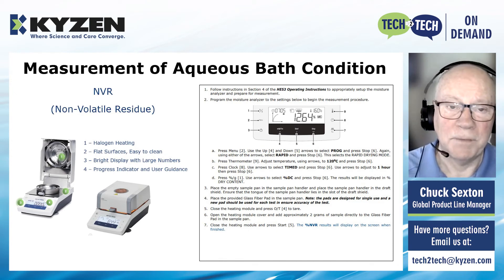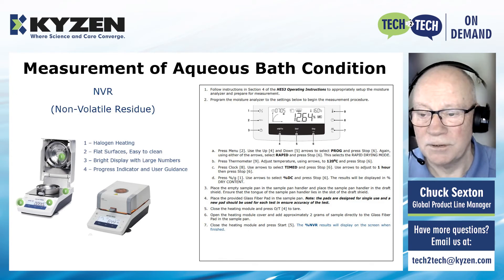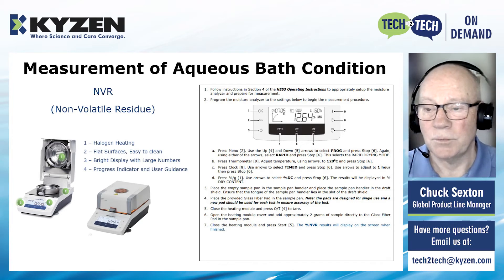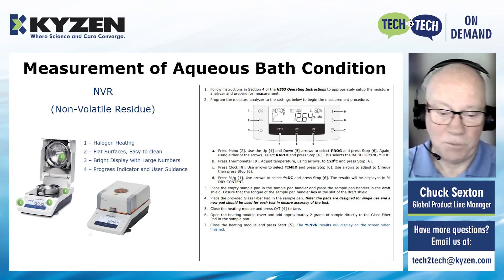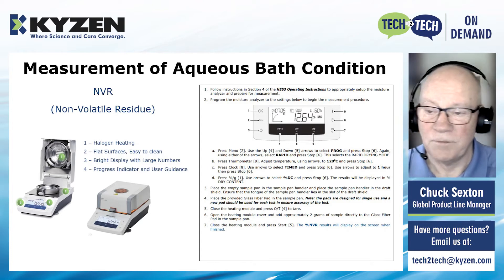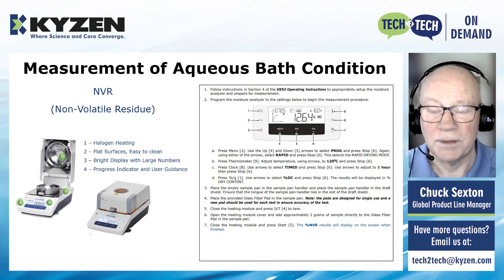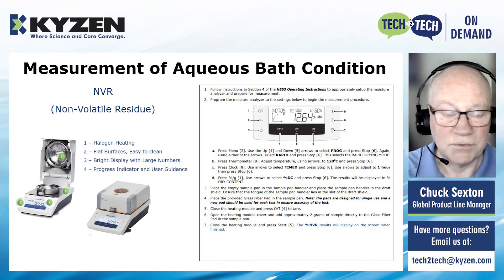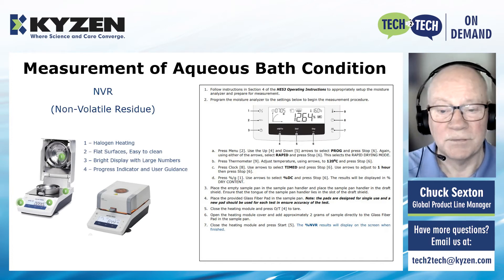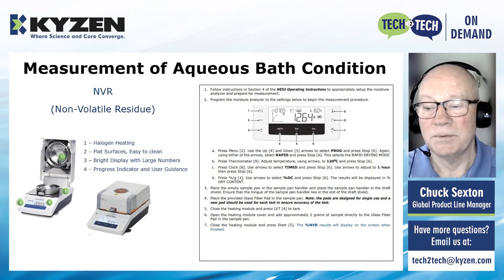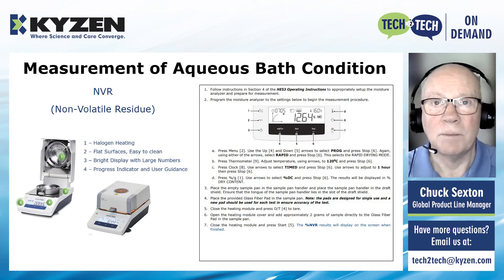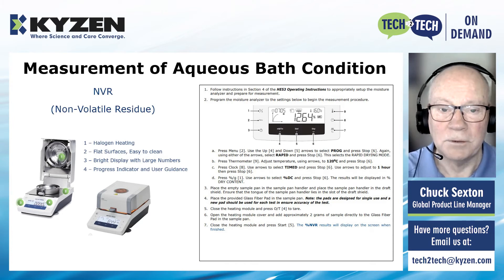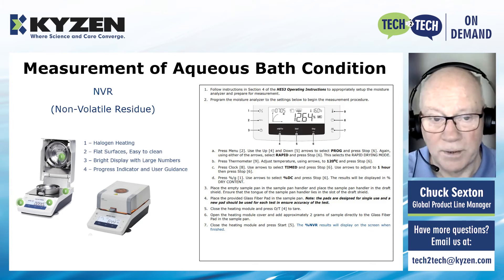NVR is another method of measuring bath condition, or how close you are to end of life. This device takes a sample, weighs it, evaporates the volatile portion, and what you're left with is the non-volatile portion — which in most cases would be the flux. So it's a measurement of soil load. We're able to identify at what point in your process the soil load is so high that you stop cleaning well.